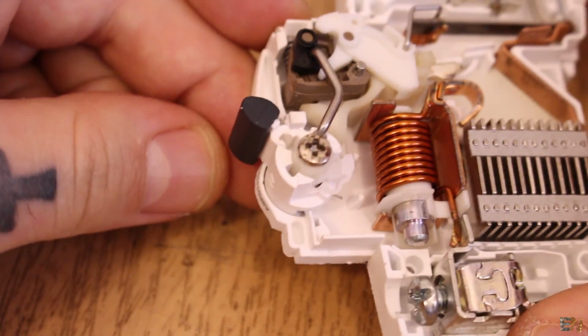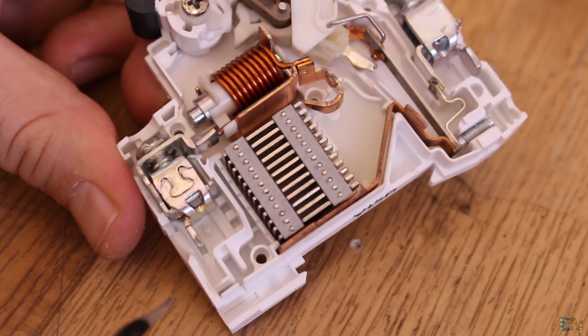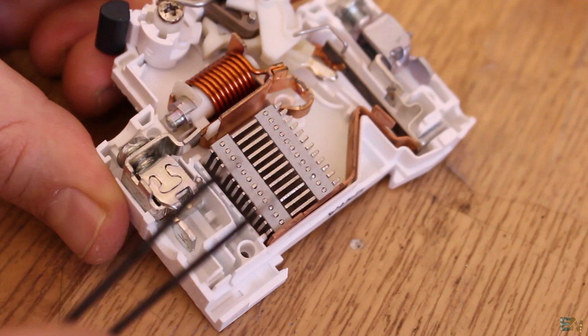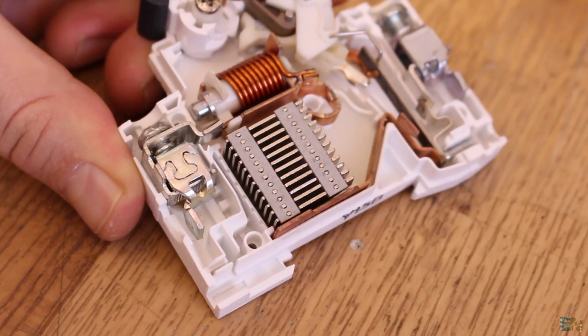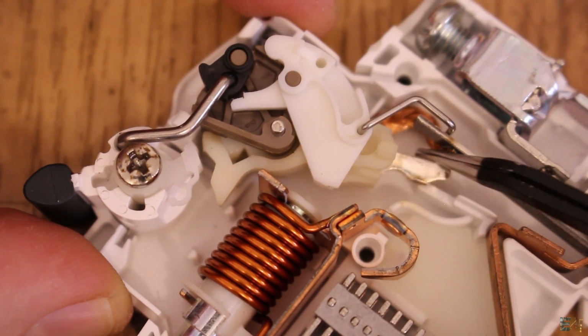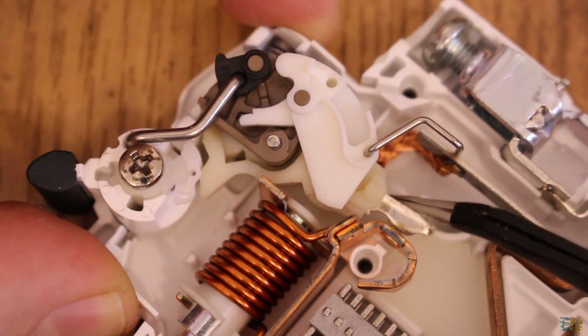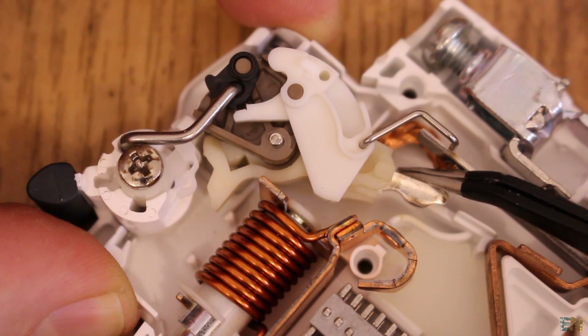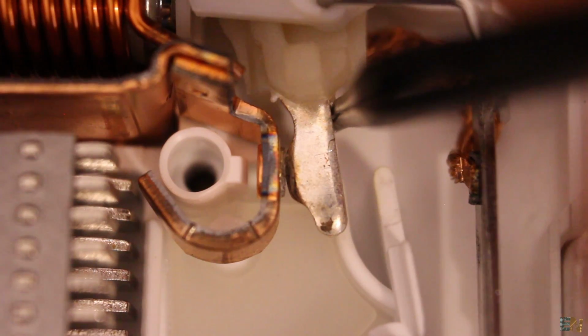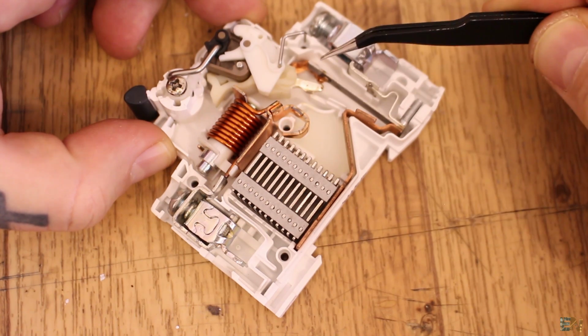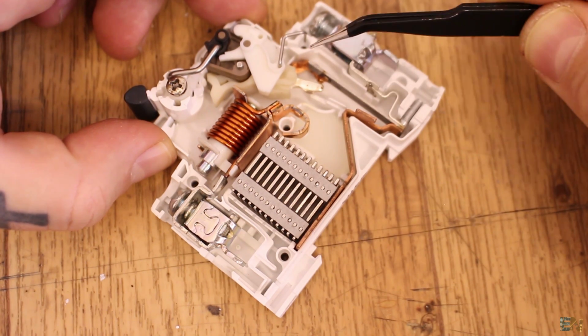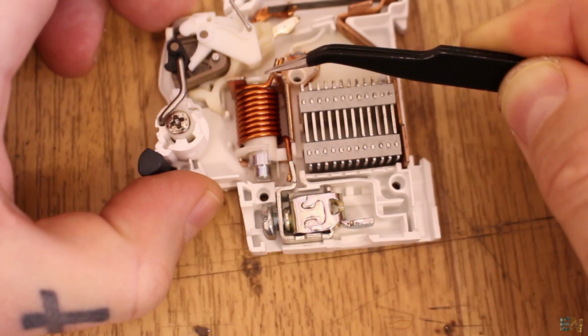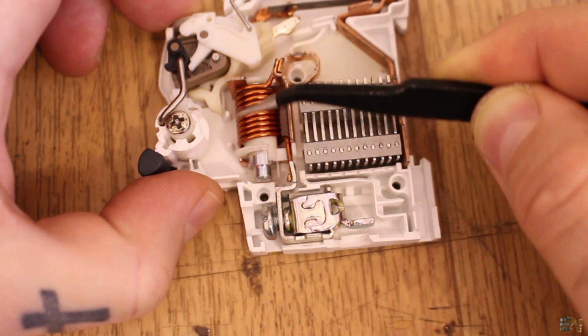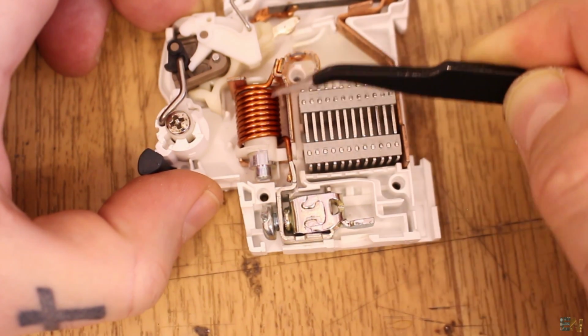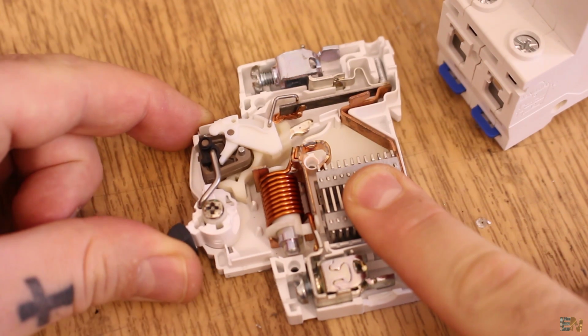In the middle we have the so-called arc driver, which prevents plasma arcs to form when the switch jumps. Above the plastic switch we have the actuator, which is the part that moves. This component will make the contact with the terminals or break the circuit when needed. And finally, the most important parts are the thermal metal strip, which is this one here, and the magnetic coil, which is this one here. Let's first see how the thermal breaker works and then the magnetic part.